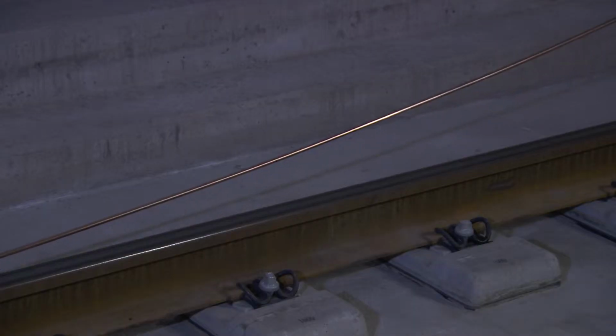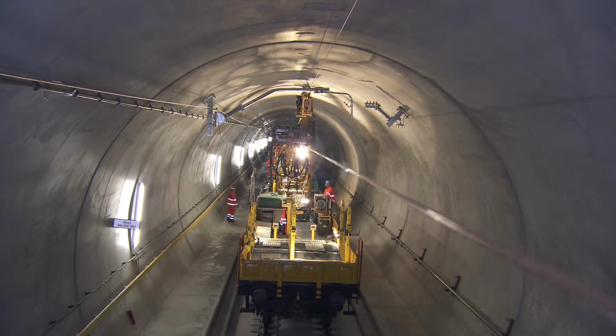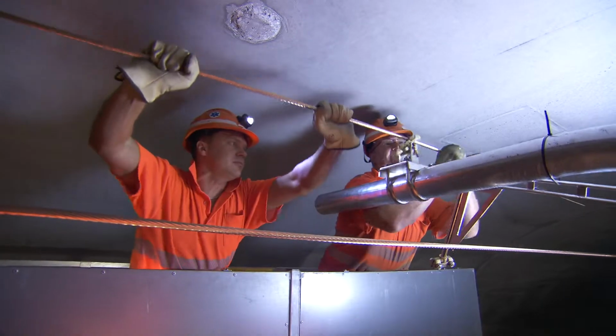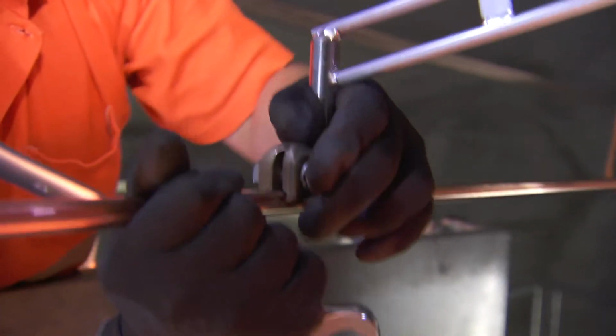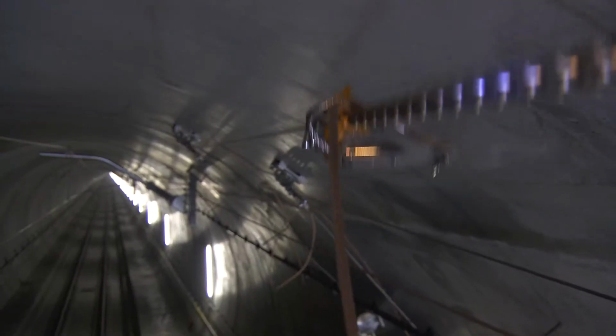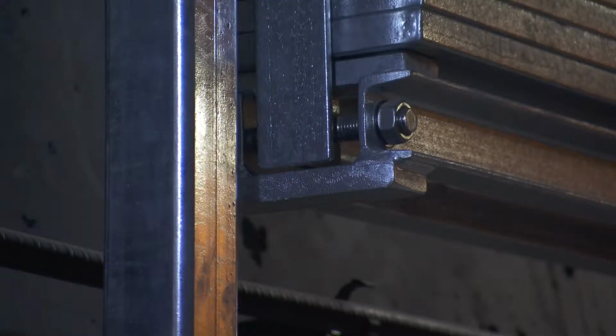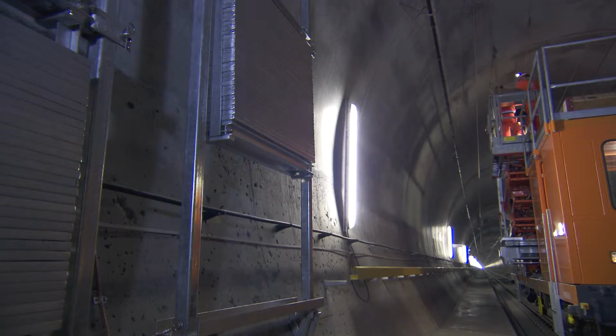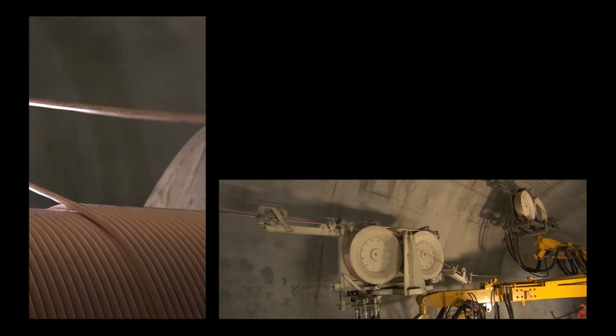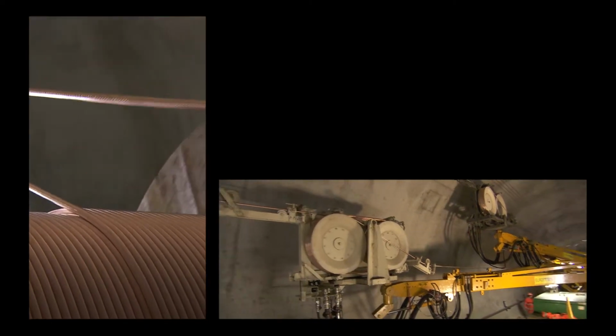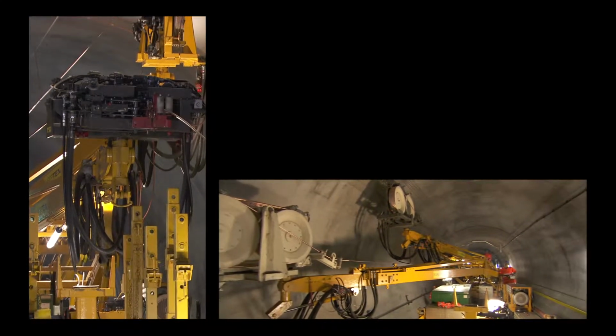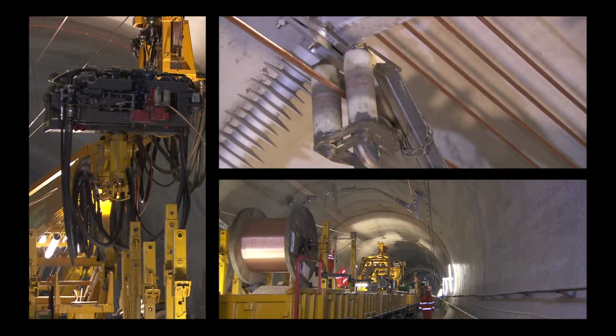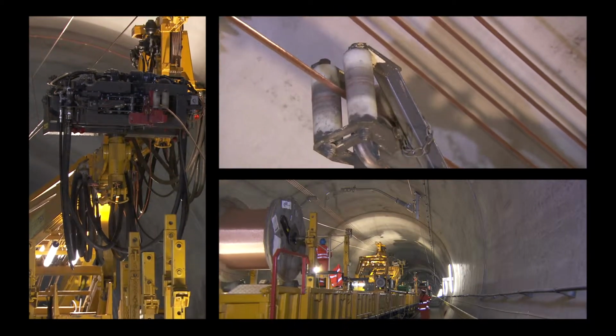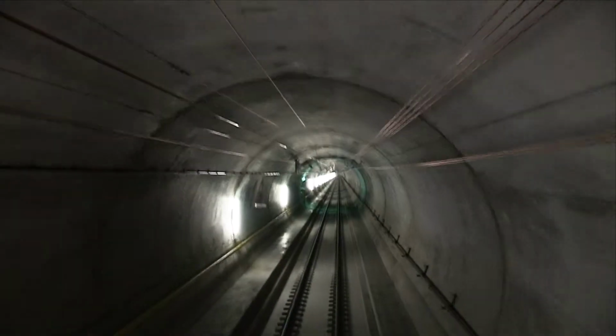For operation at 250 kilometers per hour, the contact wire has to be adjusted precisely to 5 meters 20. Weights ensure that the catenary system is tensioned. The fitters install a total of 1,400 tons of copper in the Gotthard Base Tunnel. So that several trains can use the 57-kilometer-long stretch simultaneously, 4 line feeders supply the contact wire with the necessary power.